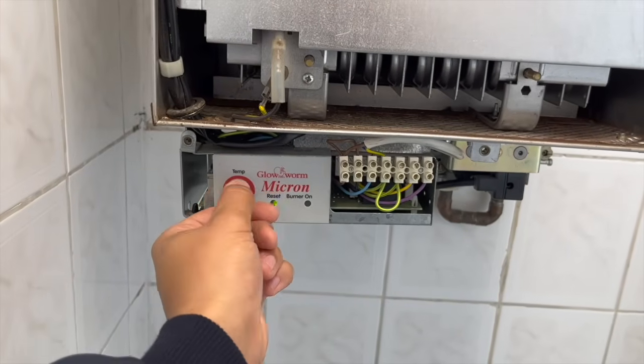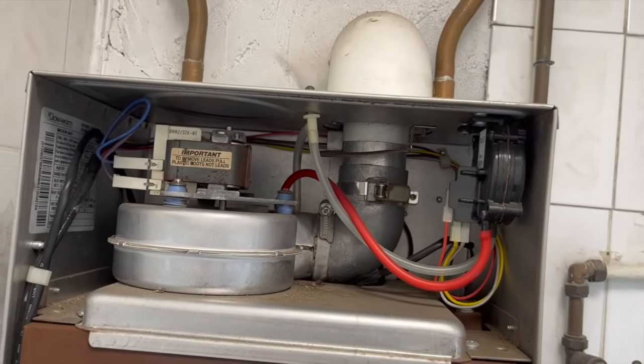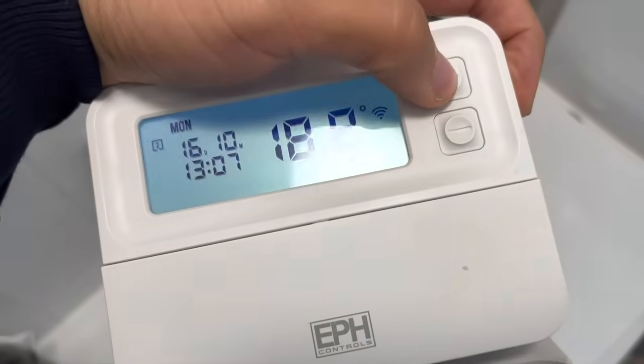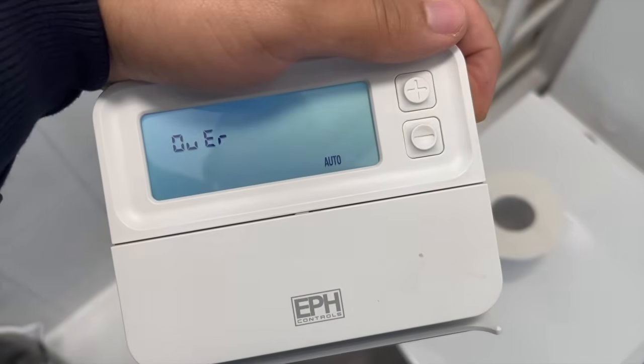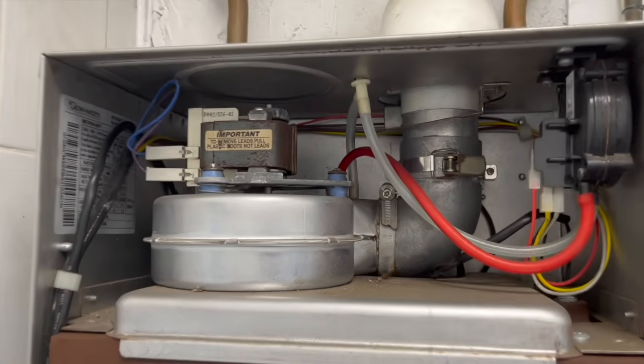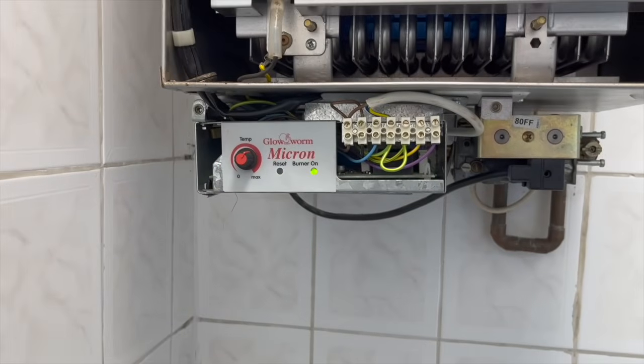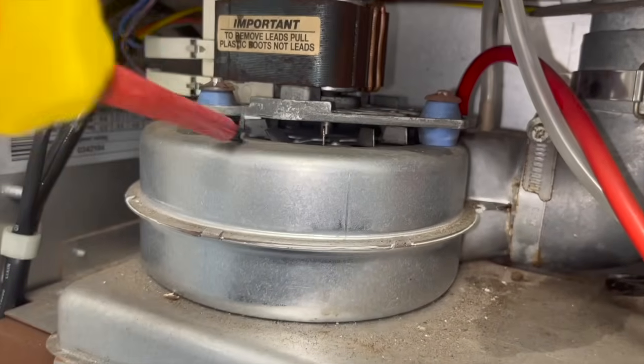For this next job we are working on a Glow Worm Micron. When I turn it on I can hear straight away it's the fan that's giving issues. The customer said their boiler is working sometimes and sometimes not. Luckily when I got there it was working so I could immediately identify it was the fan. The fan would just randomly stop spinning — I'd still get 230 volts on the live and neutral, but it would be stopped. If I got a screwdriver and pinged the fan a little bit to give it a jump start, it would start spinning again. The fan was just on its last legs, so I decided to get a new fan and swap it over.